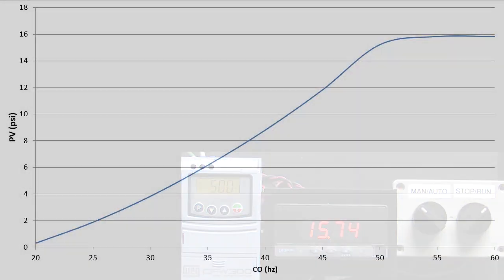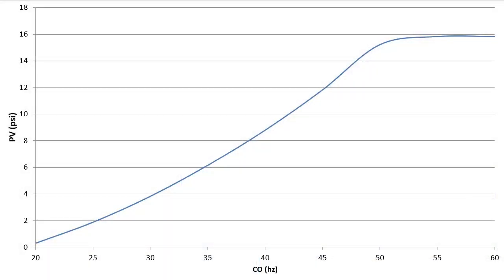If we plot that, it looks like this. So, it looks like with one valve open, we only need to run the motor at a little under 35 Hz to get the 6 psi we want.